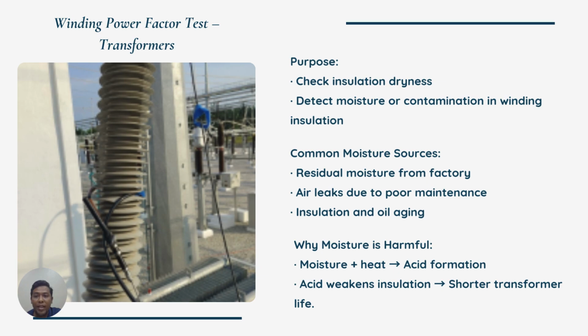Now let's look at the winding power factor test. This test checks if the paper insulation inside the transformer is still dry and in good shape. If there is moisture or contamination, the insulation can break down faster. Moisture can come from several sources. Sometimes it's left over from the factory, especially in thick insulation. Other times, leaks or poor sealing let air in. Over time, even normal aging of oil and insulation adds moisture to the system.